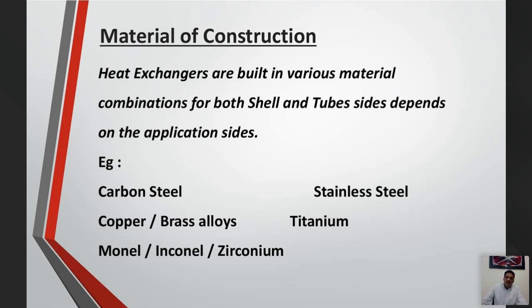These materials are all selected based on the process requirement, cost, and life of the equipment. For example, if you want to use it in a seawater application, you cannot use carbon steel or stainless steel because seawater is very corrosive. For that, you have to use copper alloys or titanium.